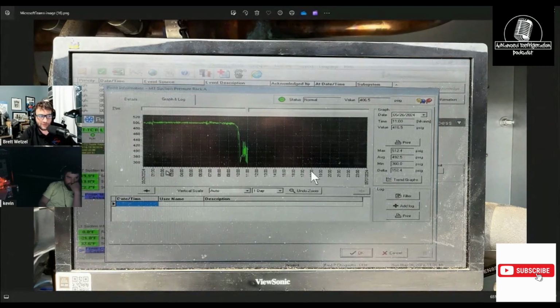Look at that job too. Isn't that cool? Why is the suction pressure like 500 pounds? Suction pressure. I think that was suction pressure. Oh, it's because rack failed. Where do you see 500? Or that's flash tank. That's the other thing I still haven't figured out. That says suction pressure. Where? At the top of the graph, it says suction pressure. Oh, it's still. I don't know why it's stuck there. That's weird. I don't know.